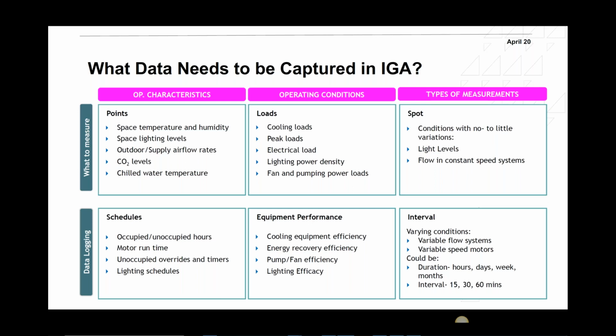So you need to take the space temperature and humidity to make sure that there is proper thermal comfort. Sometimes you go into buildings and find that the fresh air handling units are turned off completely. Now, if you go to the client and tell them, we did the measurements and found out that the FAHU is turned down to a very low speed, so that it's not, let's say, following ASHRAE 62.1, what do you want us to do? We can reconstruct the baseline to assume that this FAHU is working, and then we would update and adjust the baseline to show what would have been the energy consumption, and then start from there. Or if you want us to keep the FAHUs closed, it's up to the client to decide. Normally, we would advise them to make sure that the equipment is working properly, especially when it comes to indoor air quality and health and safety. So we need to advise the client that they need to fix these things.